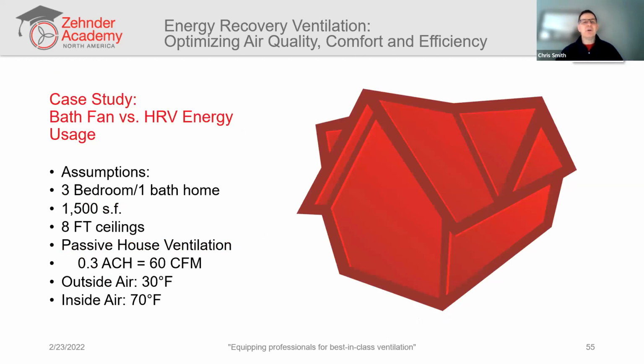So let's look at an example. Here's just a real simple case study. A 3-bedroom, 1-bath home. Let's say it's 1,500 square feet. Let's say we want an air change rate of 0.3 air changes per hour. That's the ventilation rate, or 60 CFM is the ventilation rate for this house. That's pretty typical, by the way. Let's say the outdoor air is 30 degrees and the indoor air is 70. That gives us a nice round 40 degree delta T.